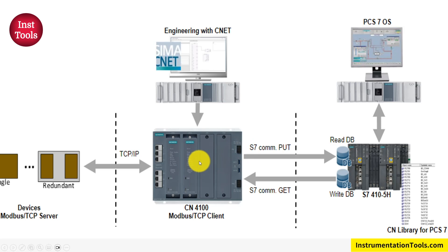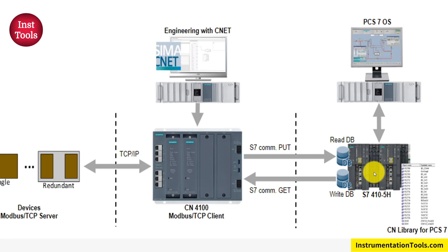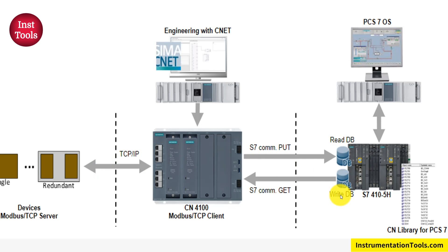From CN4100, there is a direct ProfiNet connection to the S7-400 or S7-410 AS station. Some data blocks (DBs) in the S7-410 are allocated to hold the Modbus data. We use S7-PUT and GET instructions, which are popular instructions when dealing with Modbus devices in the CFC editor or when programming the S7-410. Those data blocks are then directly shown in our OS station.